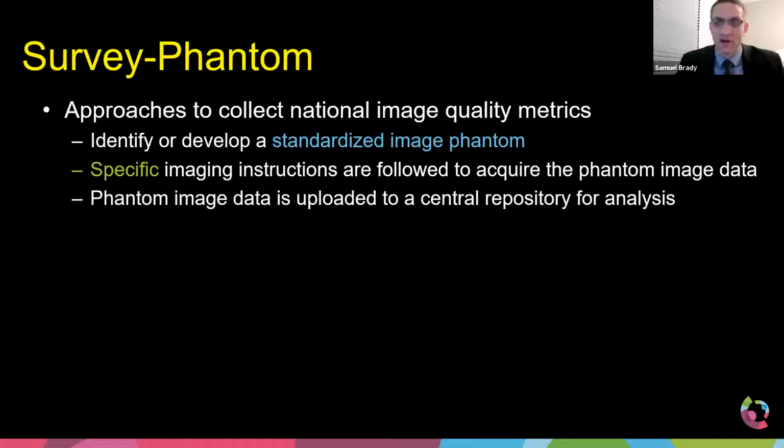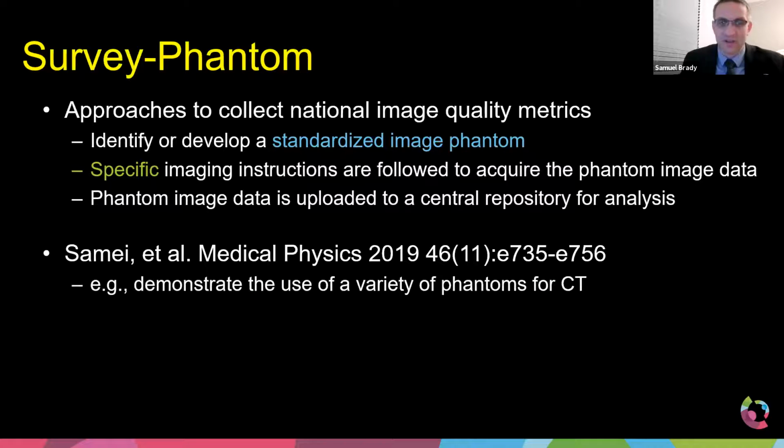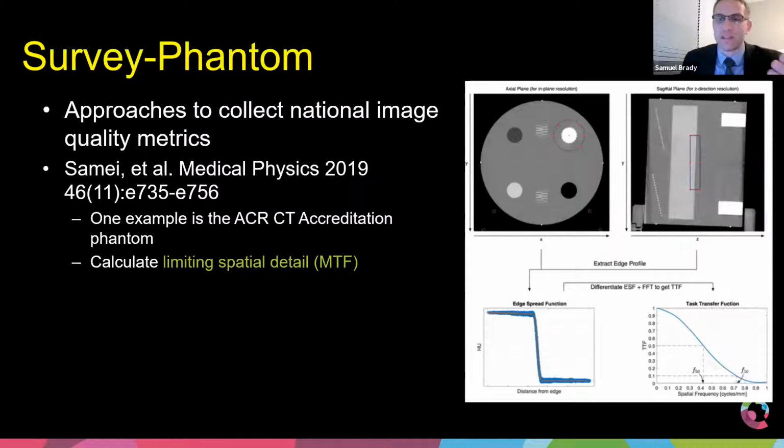And then once you do that, all of that data can be uploaded, the scans of those phantoms, and then all of that data will be processed in one location. So it's a little simpler in the sense that the hospital, all they have to do is scan the phantom. And if they do it right, and upload the data, they're finished with that. So in a publication in 2019, Dr. Samei, I was part of this group, we looked at how could we do this for CT. So I'm going to give you an example of one way we came up with to do this for CT.